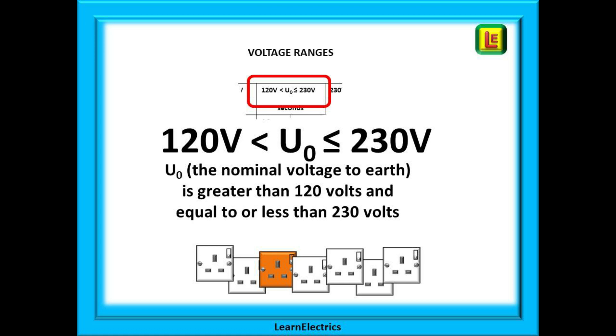It is not the voltage you measure — it is the assumed voltage. We always assume 230 volts for all of our calculations, even if the circuit measures 240 volts. So this arrangement of symbols is saying: U0, the nominal voltage between line and earth, is greater than 120 volts and equal to or less than 230 volts. Greater than 120 volts means 121 volts or above; equal to or less than 230 volts means anything up to and including 230 volts.